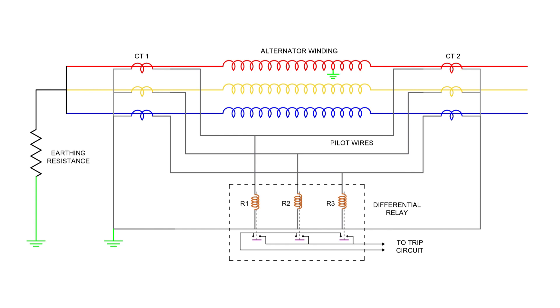Now, let's discuss how this works during faults. Suppose an earth fault occurs on phase R. Due to insulation breakdown, current will now flow through the fault and reach the ground via the earthing resistance. Because of this, the currents in CT1 and CT2 for phase R will become unequal. The difference in these currents will flow through the relay coil R1, which then activates the trip circuit, isolating the alternator.